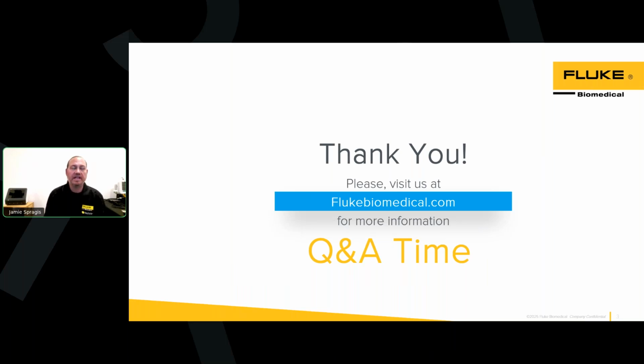And again, that's built into the instrument and OneQA. When you're building your procedures in OneQA, it'll ask you what electrical safety standards you're testing. Not only will it set the parameters for you, but it navigates you through the IEC standard. The only thing it can't do is have 2 different standards on a procedure. So you couldn't do aspects of 60601 and aspects of 62353. Although we're hearing there are a lot of blended approaches like that, so that may be something we do in the future. But right now, you essentially could have 2 tests. You could do a testing standard for the 62353 and then a testing standard for the 60601.